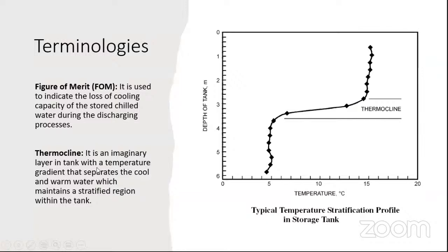Thermocline is an imaginary layer in the tank with a temperature gradient that separates the cool and warm water. See, like in this curve, this is the depth of the tank. Let us see this as a tank. This is the depth of the tank, and this is the temperature axis. So at 15-degree temperature, at the hotter, it's the hotter water, the hot water is at the top, the cold water is at the bottom. So what is between these two? Between these two, that colorful zone that we saw in the previous CFD, that is the mixing zone. That mixing zone is called the thermocline, that contains the temperature gradient between the warm and cold fluid.